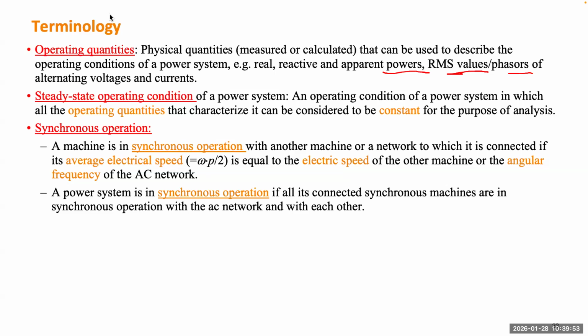Why do we use the electric speed? Because their physical speed can be very different, depending on how many poles you have. In order to generate 60 Hertz AC electricity, if the generator only has 2 poles, such as a round rotor generator, the rotor speed, actual speed, will be 60 times in 1 second, which is 60 Hertz. If you have 4 poles, like 2N and 2S, then the rotational speed can be 30 Hertz, so the electric speed can still be 60 Hertz, right?